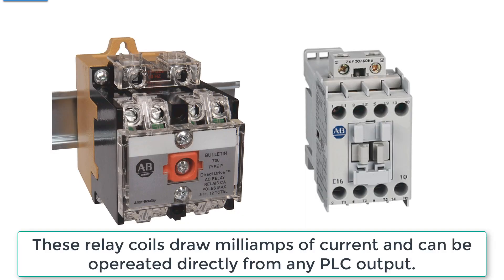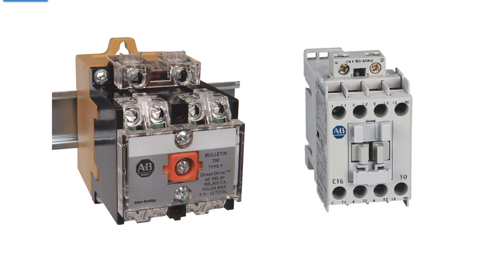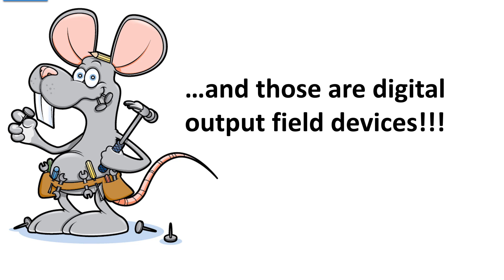For other devices, these are relays — not motor starters, but straight contactors. Power is applied through an output from a PLC at the top, and the four large sets of contacts can be used to control electrical devices that require a lot of power, such as heaters, high-power lighting, etc. If you look closely under the screw terminals, you see symbols that look like normally open contacts, indicating that the four contact sets on this relay are all normally open — these are digital output field devices.